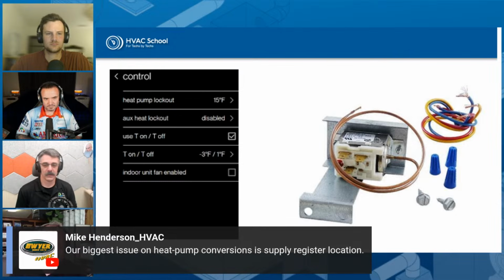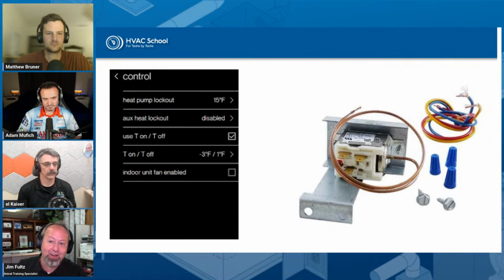The comment that came up here, I think, is what my mind's been going to as well. That's all fine and good, but when you're taking a gas furnace out and putting a heat pump in, you already have the ductwork and all of the registers in. If you're going to do this, you're going to that homeowner and saying, by the way, while we're here, we need to give you the cost of replacing all of your registers and making sure that we're blowing air in the right place. Sometimes that's possible. Sometimes the register location is just a terrible location, and unless you're going to relocate something, that's a hard sale. That's a really hard sale to deal with. Yeah, it can be a real big problem and a real big challenge, getting that done properly.